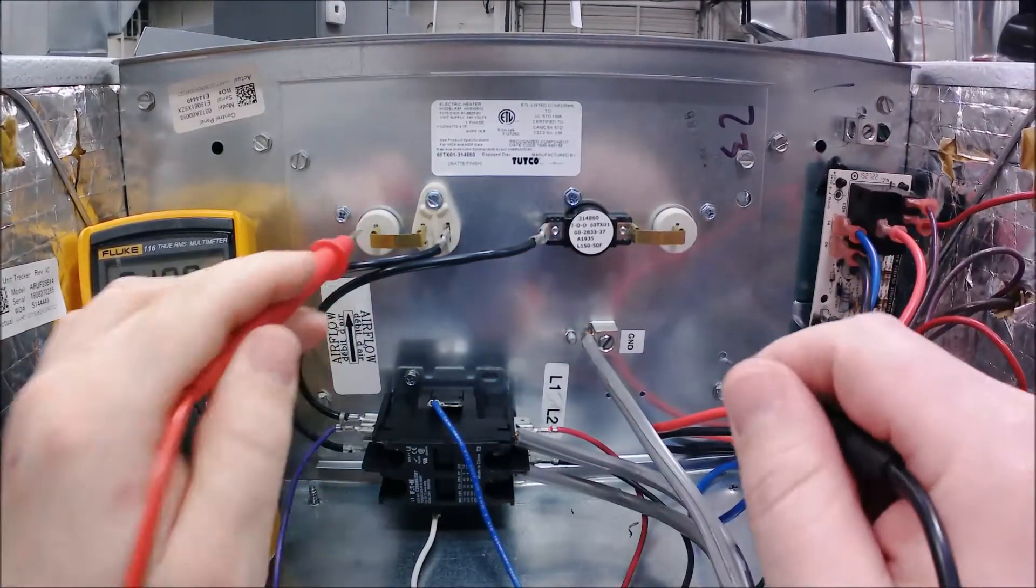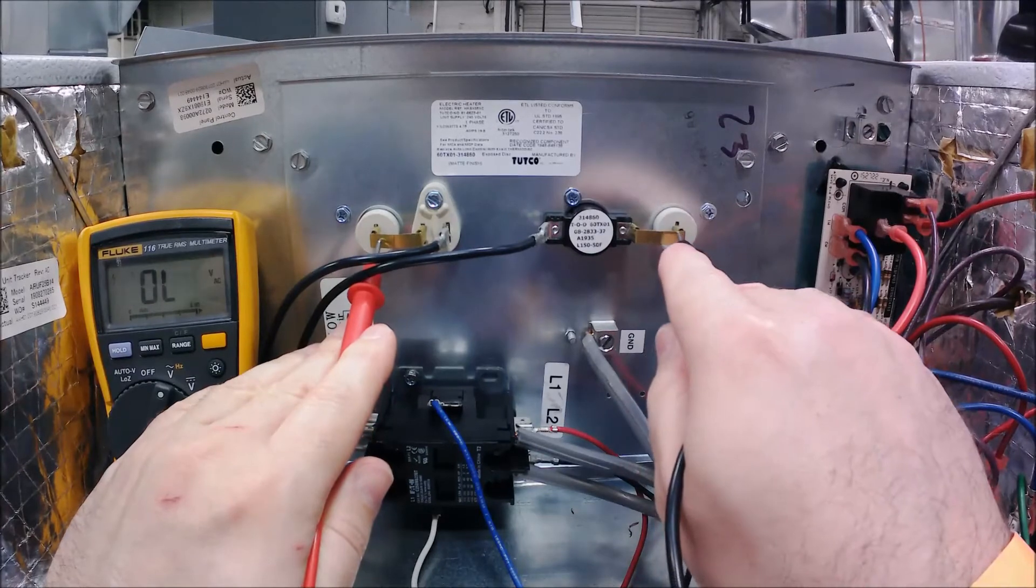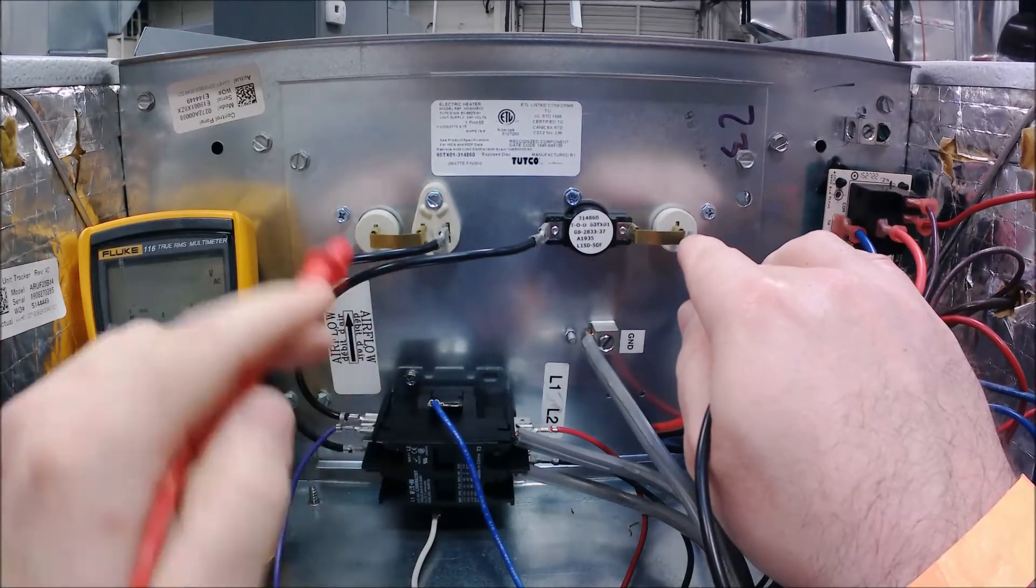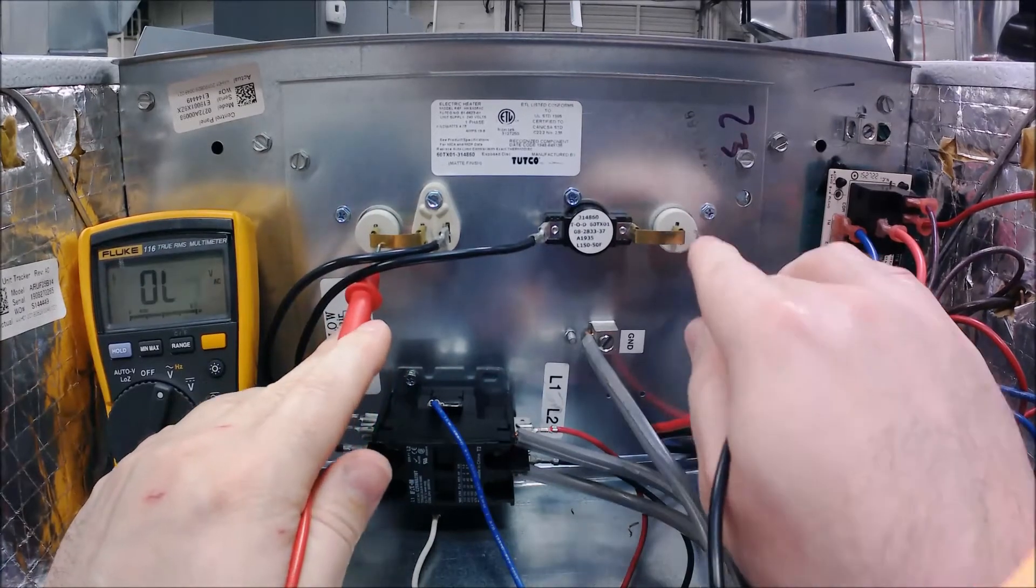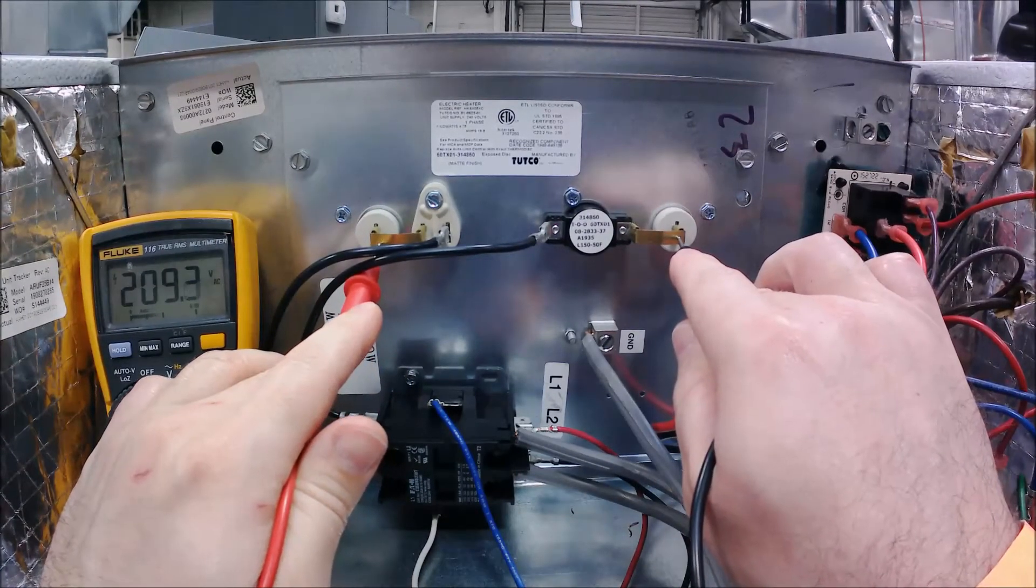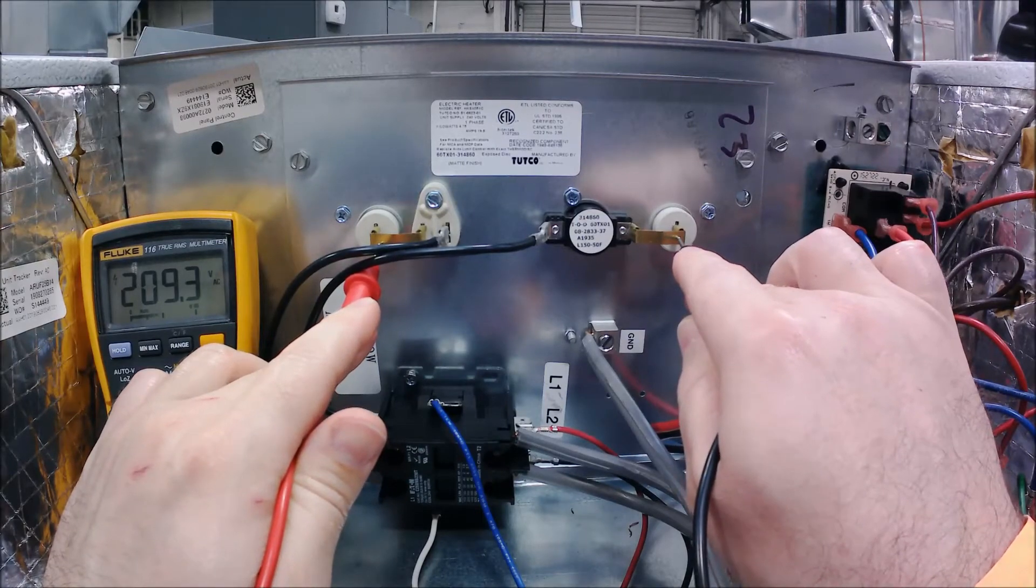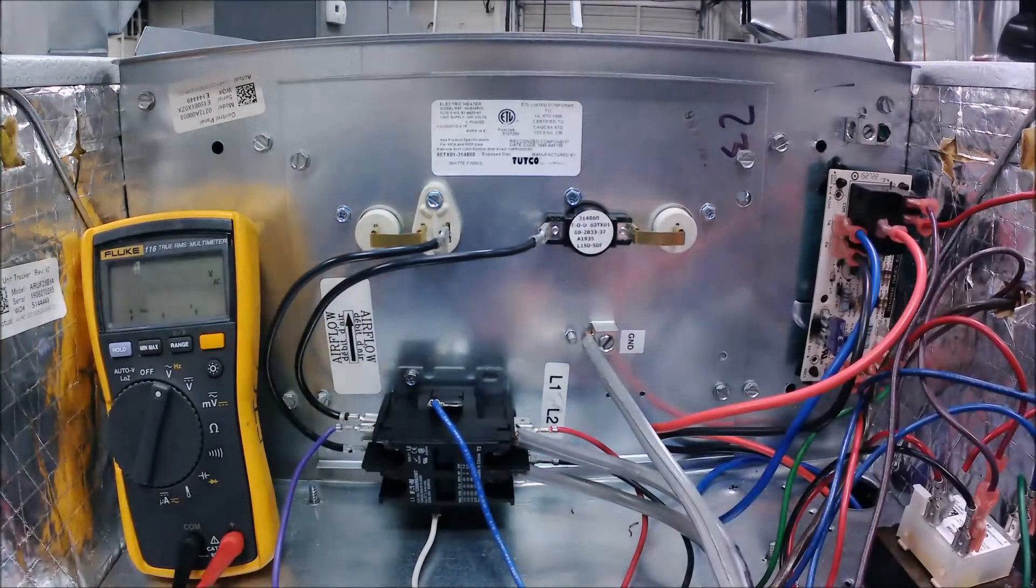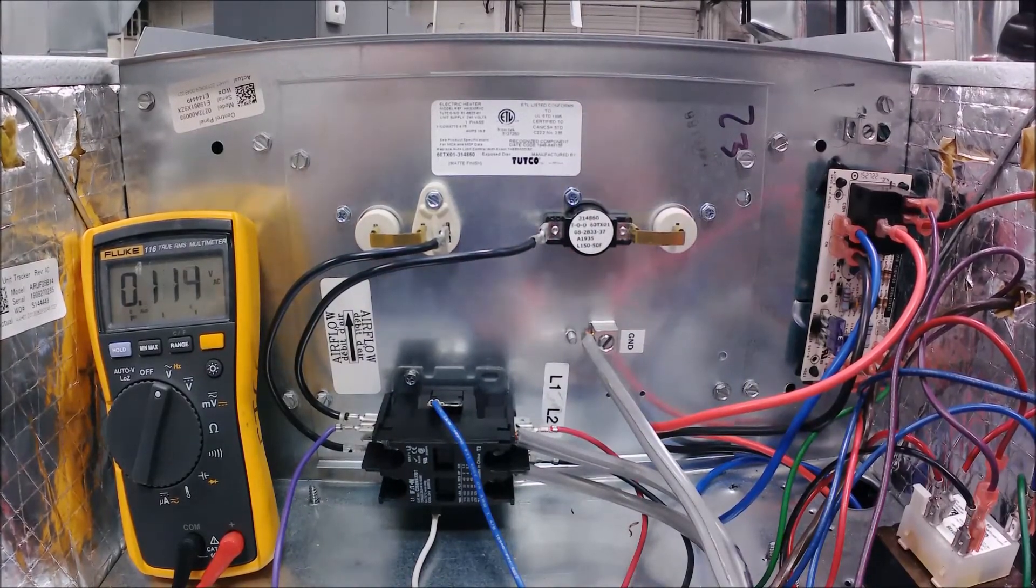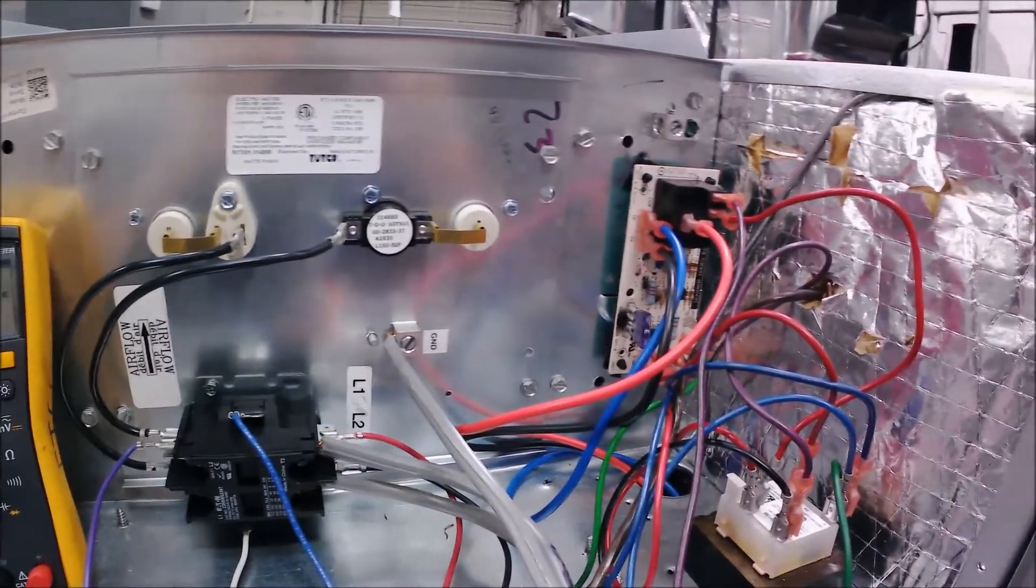For my electric heater, this is my heater strip right here - these two ceramic blocks right here, that is the beginning and end of my electric heater strip. So you can see here that I've got the full voltage going to it, and of course we've already done the amp draw, so everything is good.